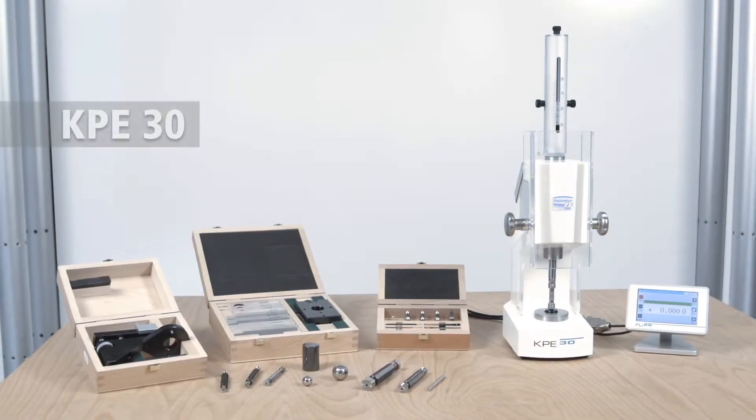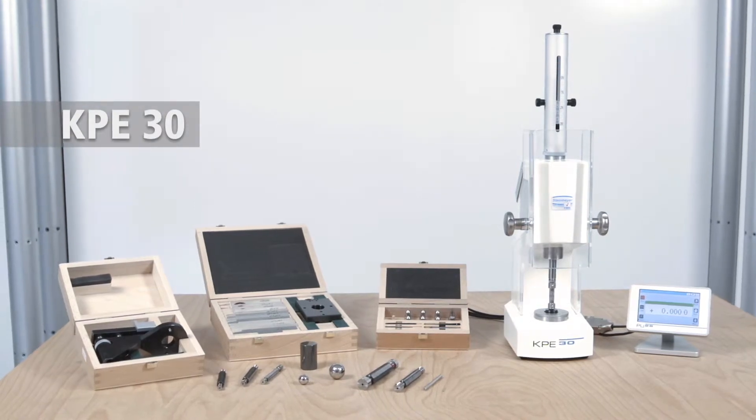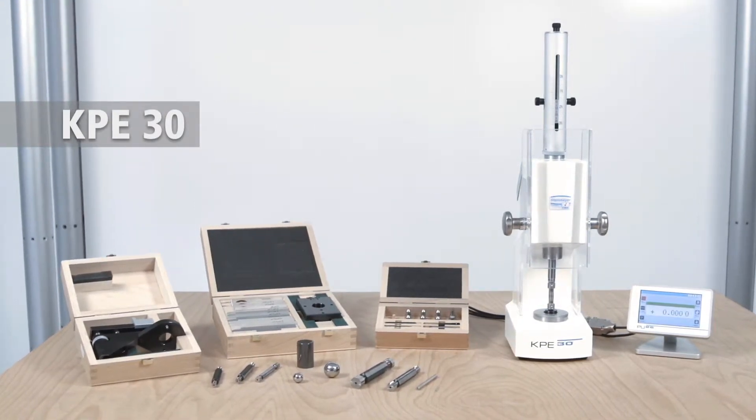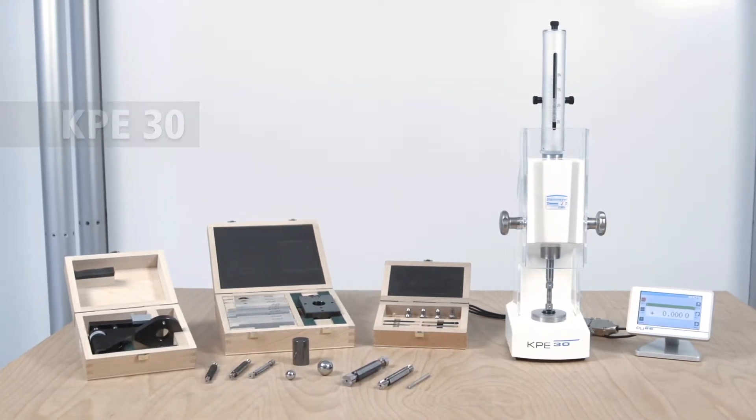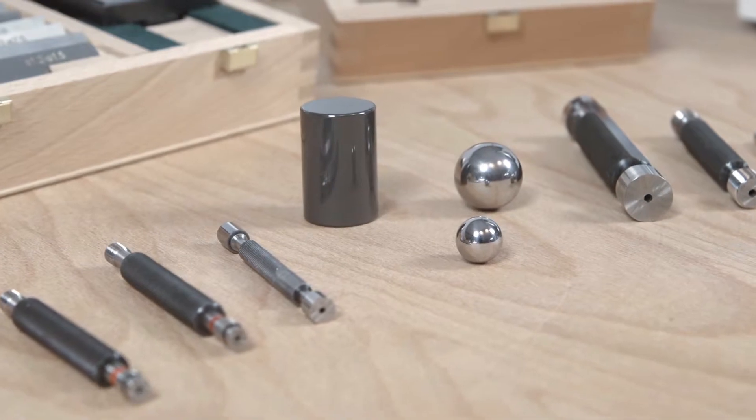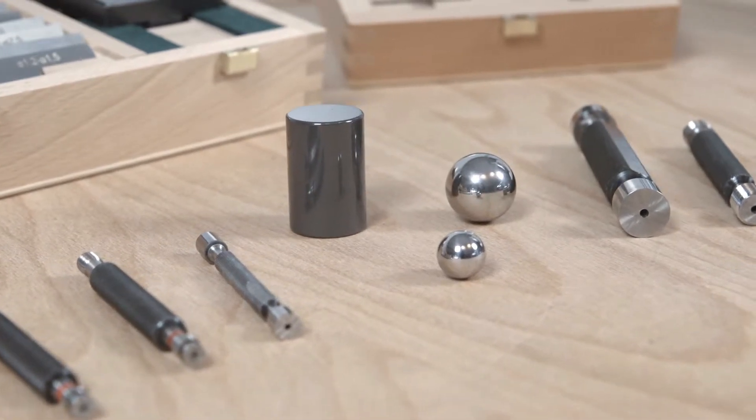Every gauge is exposed to wear and aging and therefore has to be checked on a regular basis. The KPE30 from FeinMess Suhl embodies a simple solution to test plug gauges of every shape and kind up to a size of 30 mm.